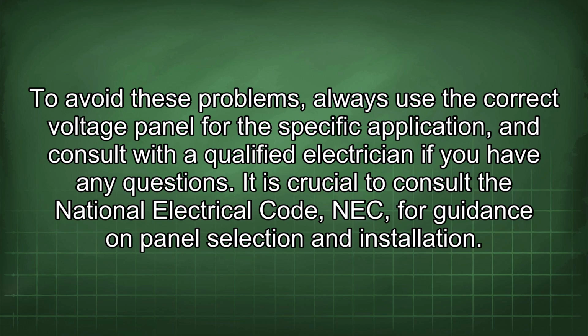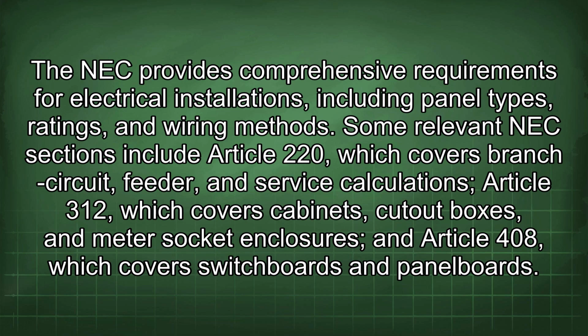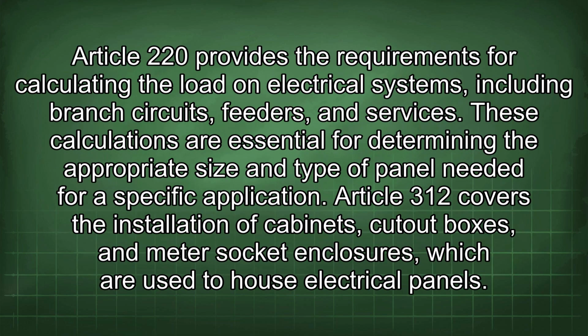It is crucial to consult the National Electrical Code, NEC, for guidance on panel selection and installation. The NEC provides comprehensive requirements for electrical installations, including panel types, ratings, and wiring methods. Some relevant NEC sections include Article 220, which covers branch circuit, feeder, and service calculations, Article 312, which covers cabinets, cutout boxes, and meter socket enclosures, and Article 408, which covers switchboards and panel boards. Article 220 provides the requirements for calculating the load on electrical systems, including branch circuits, feeders, and services. These calculations are essential for determining the appropriate size and type of panel needed for a specific application.